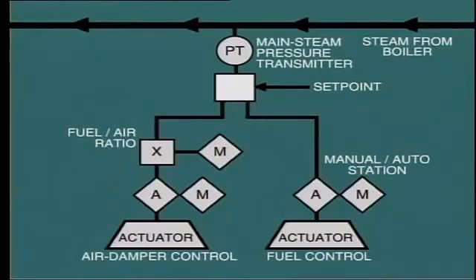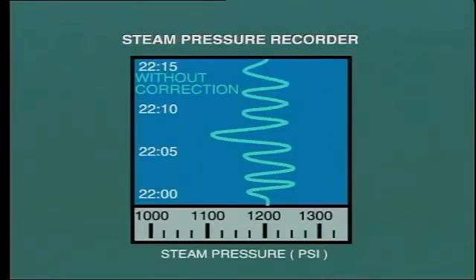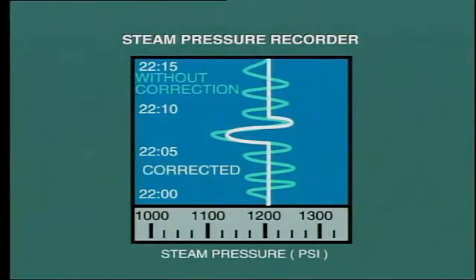The cumulative delay from this control system results in a fluctuating steam pressure. This situation could be vastly improved by adding a second element to the control system — measuring the steam flow from the boiler and using this as an anticipatory signal. We know that increased steam flow will result in a falling steam pressure within about 10 to 15 seconds. However, by applying the steam flow signal to the master controller, the corrective action is started in advance, providing increased combustion at about the same time as the pressure begins to fall. The actual resulting pressure then trims the controller settings.